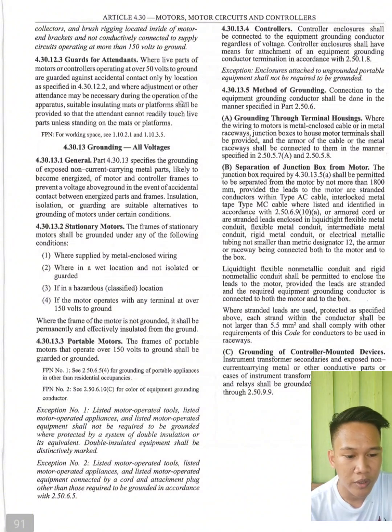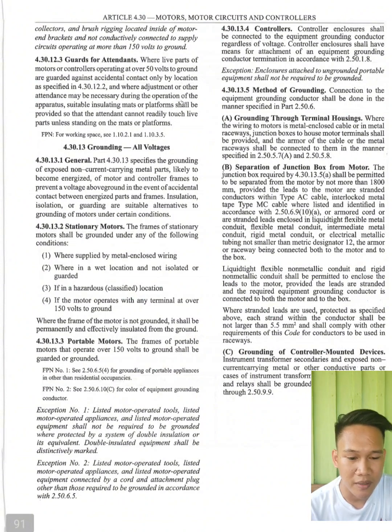The junction box required by 4.30.13.5a shall be permitted to be separated from the motor by not more than 1,800 mm, provided the leads to the motor are stranded conductors within Type AC cable, interlocked metal type MC cable listed and identified in accordance with 2.50.6.9.10a, or armored cord, or are stranded leads enclosed in liquidtight flexible metal conduit, flexible metal conduit, intermediate metal conduit, rigid metal conduit, or electrical metallic tubing not smaller than metric designator 12, the armor or raceway being connected both to the motor and to the box.